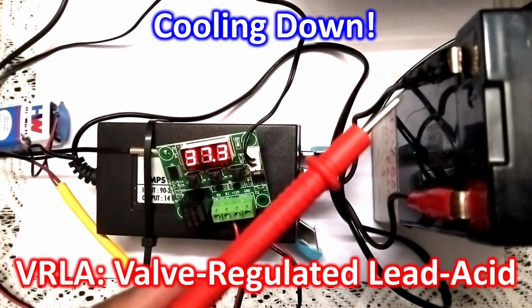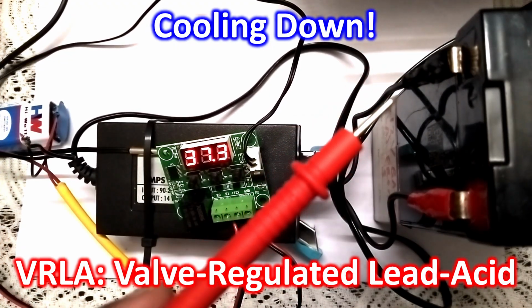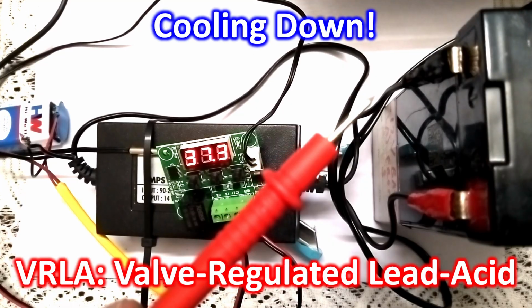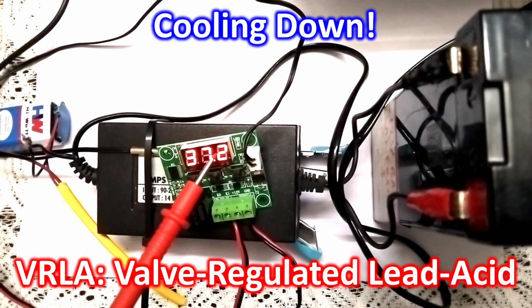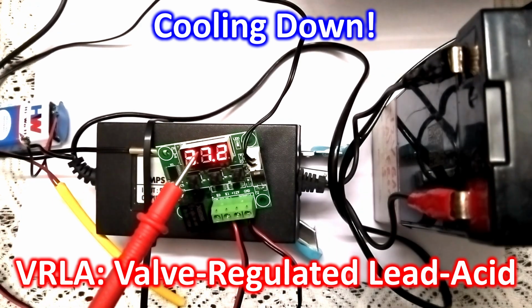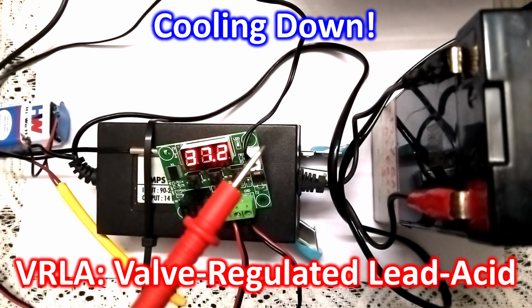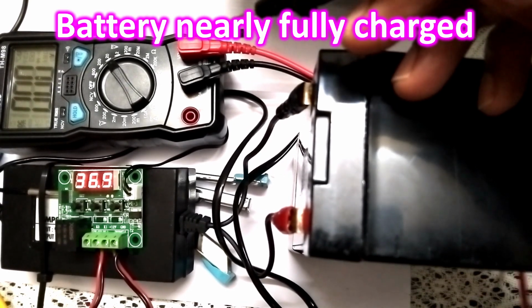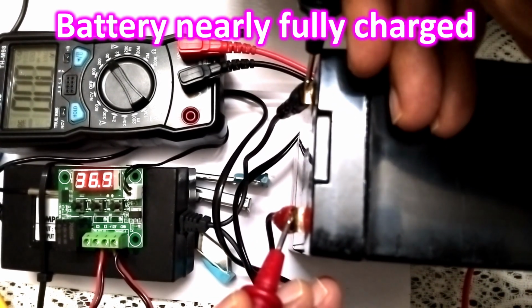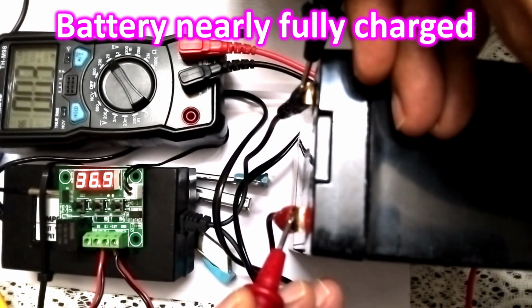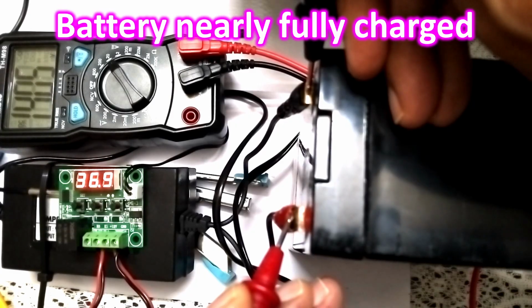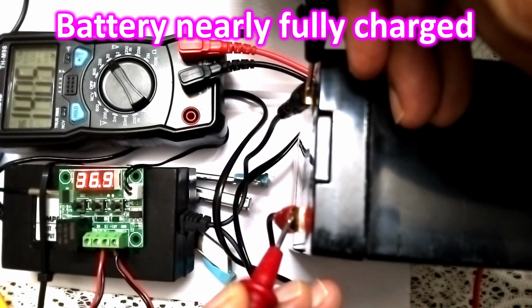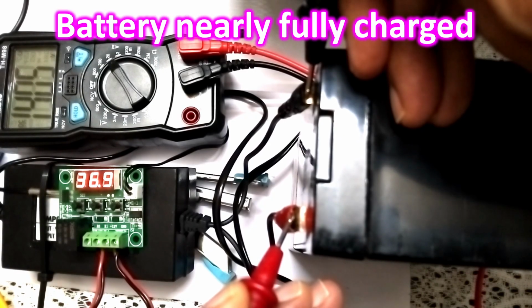Then when you open the door of the enclosure, usually you feel the smell of the acid fumes, sulfuric acid fumes, even though it is only dilute sulfuric acid. So with the good ventilation, the temperature is coming down. That's another option for decreasing the temperature when charging is going on. Charging has been going on for quite some time now, and I'm just checking the voltage. It is seen as 14.05, but that is not the battery voltage. That is reflecting the charger voltage. The charger gives a voltage of around 14, and that will be reflected now because the battery is probably nearly full. So the voltage is seen like that.